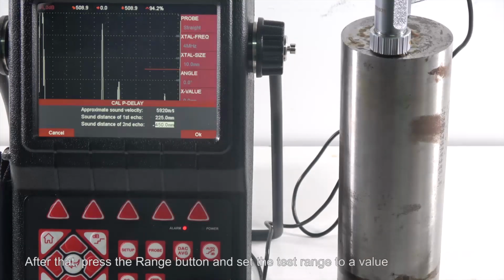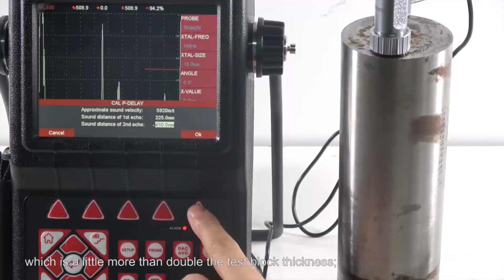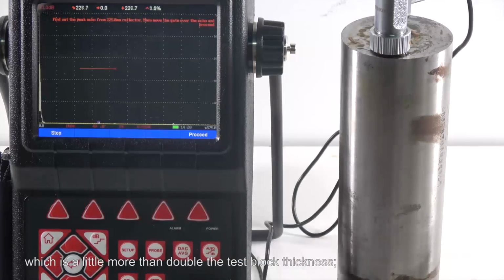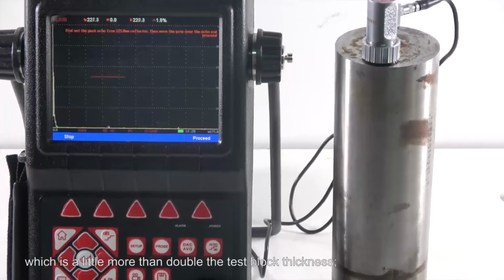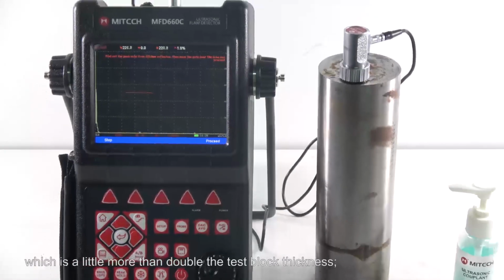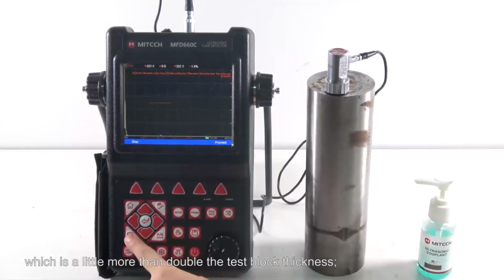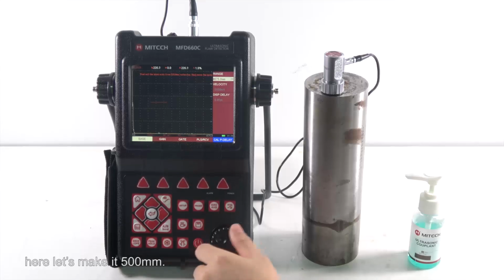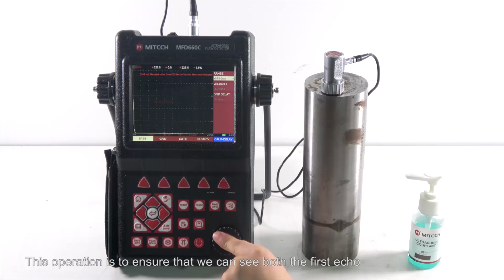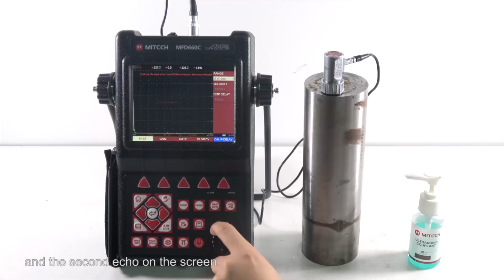After that, press the range button and set the test range to a value which is a little more than double the test block thickness. Here, let's make it 500 mm. This operation is to ensure that we can see both the first echo and the second echo on the screen.